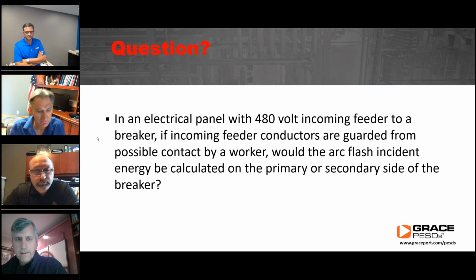If I calculated the incident energy on the source side of that breaker, in particular if that breaker is connected directly to a transformer, from the load side of a transformer to the first main breaker there is almost always a lot of incident energy. The main breaker will usually lower that to a much lower level. So one school of thought is to be extra cautious.